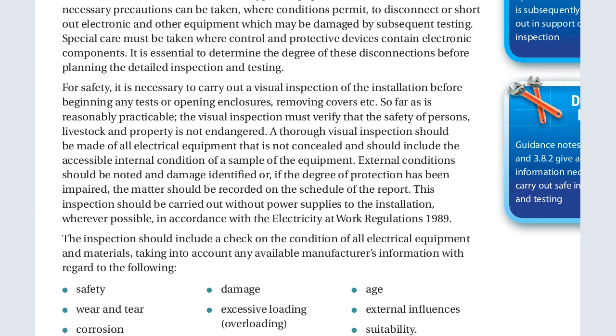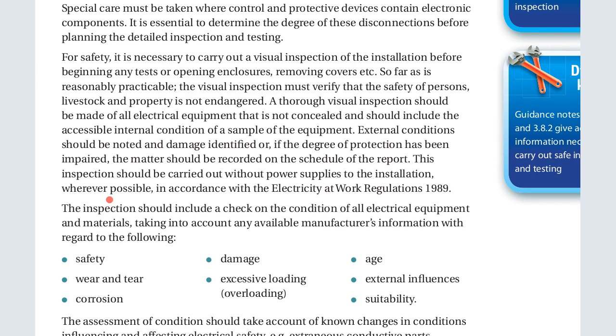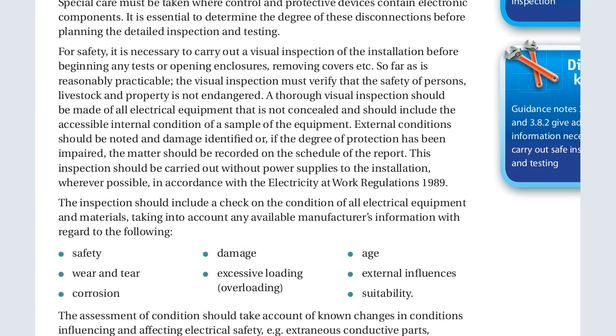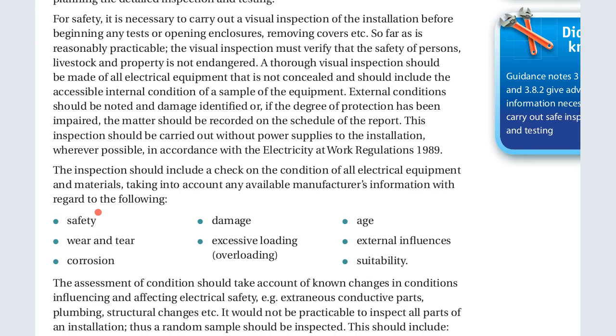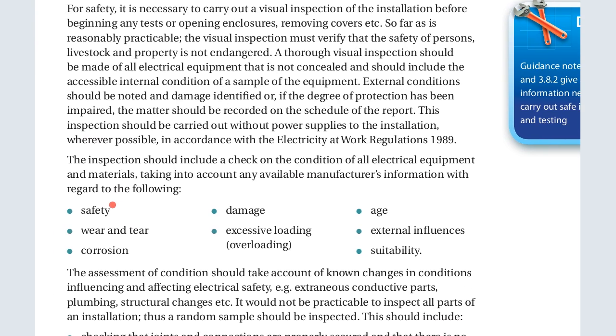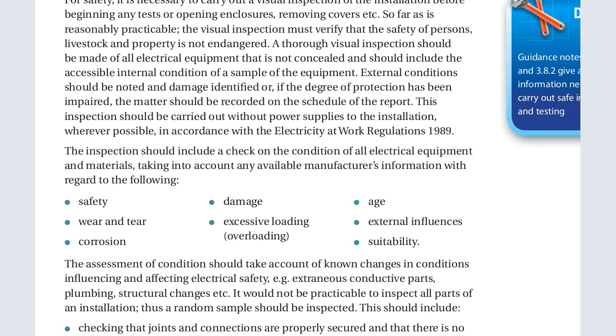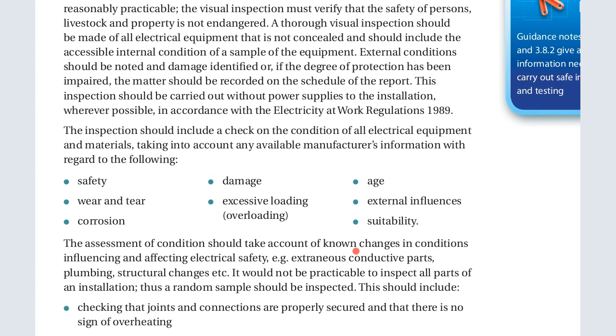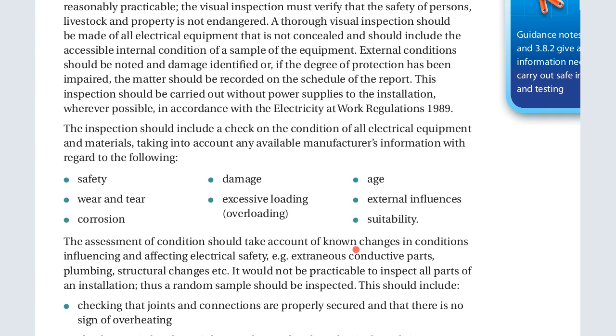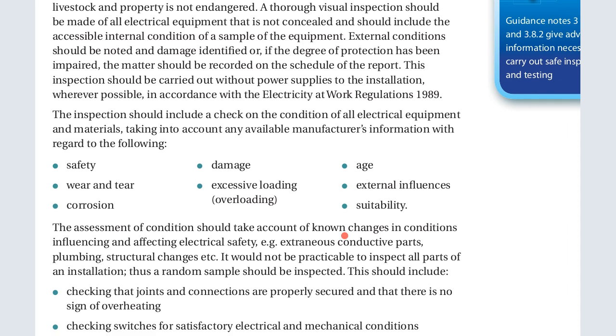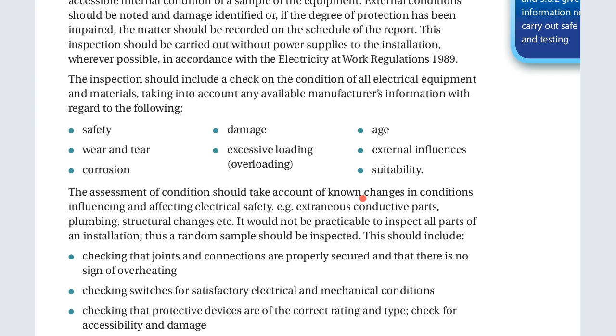That is, the external condition should be noted and damage identified. Or if the degree of protection has been impaired, the matter should be recorded in the schedule of the report. So this inspection should be carried out without power supply to the installation. The inspection should include a check on the condition of electrical equipment and materials, taking into account any available manufacturer's information with regard to the following.